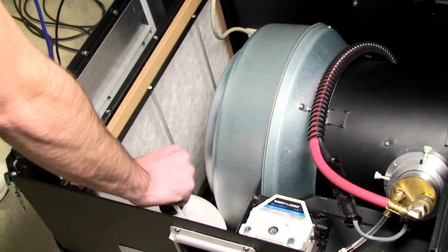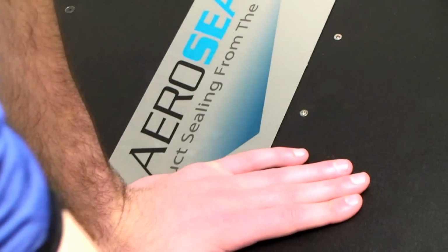My house, when I bought it, I knew was a 1980 vintage home and therefore had extremely leaky ducts. I didn't realize they were as leaky as they were. One of the only systems I thought would work for me was an aerosol-based injection system. My duct layout's very complicated and not accessible, so an aerosol injection system was a very good fit for me. And when we did it, we reduced the leakage from over 600 CFM down to about 80. So that's like an 80% reduction in leakage. Can you imagine how much waste I had in this particular house? But I knew that going in. I was willing to buy this house knowing that there was a technology that could help me fix such a significant problem.